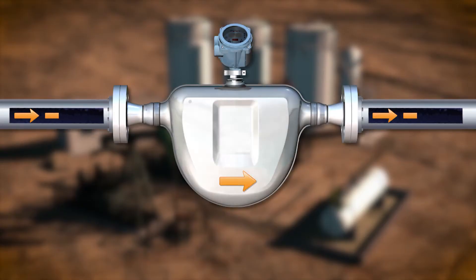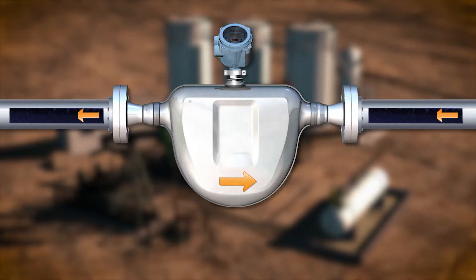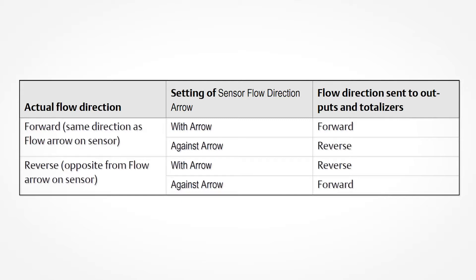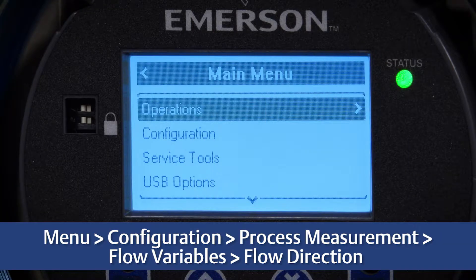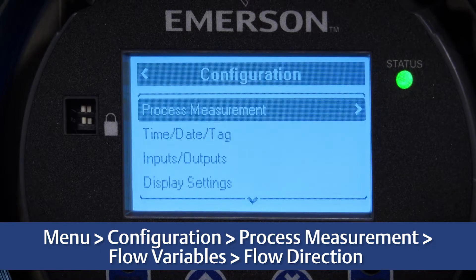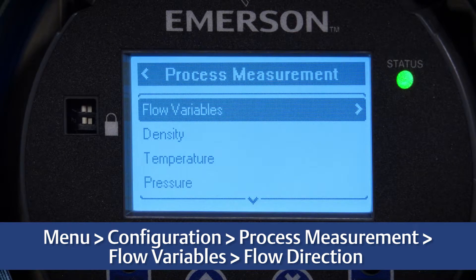The sensor works equally well with flow in either direction. The sensor flow direction arrow establishes a convention of forward flow to accommodate customers who need to define forward and reverse flow for process purposes. The sensor flow direction arrow interacts with milliamp outputs, frequency outputs, and totalizer direction to control how flow is reported by the outputs and accumulated by the totalizer. Using the display on the 5700 transmitter, select Menu > Configuration > Process Measurement > Flow Variables > Flow Direction.